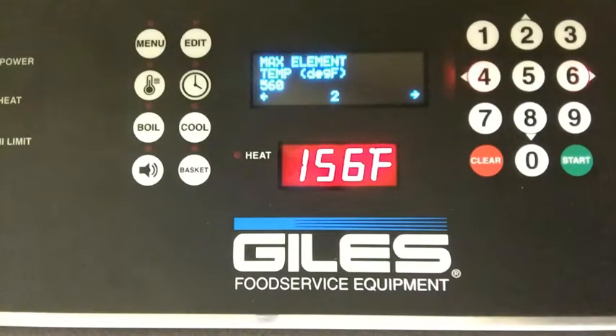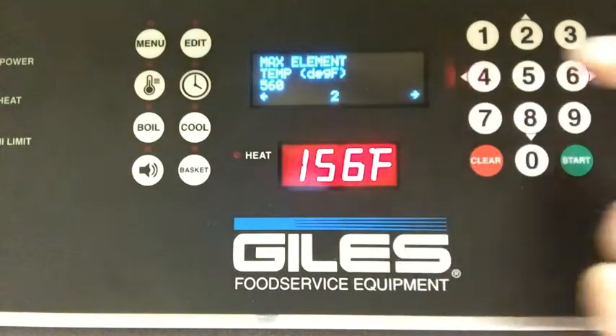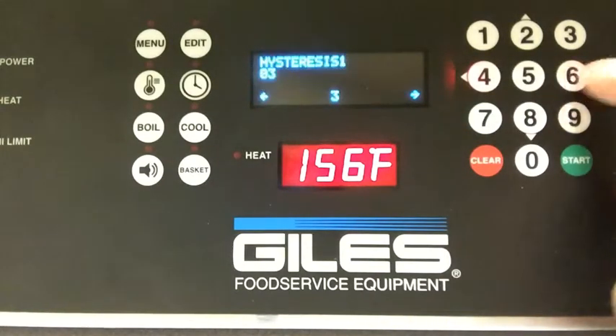If you bring this up too high, you run the chance of fire on an element that may have a little bit of a coating of oil on it. If it gets up high enough, it can actually strike that into a fire. So we want to do that as safely as we can, bring it as low as we can. It will throw a message that says max element temp has been exceeded if you get beyond that and it decides to shut down. But 560 is a good number for this machine.